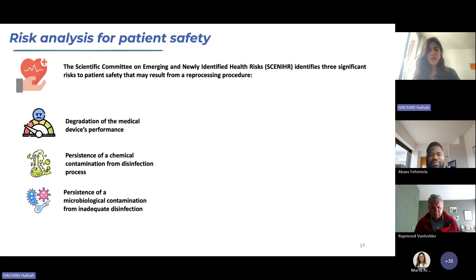So quickly, regarding the risk analysis, the Scientific Committee on Emerging and Newly Identified Health Risks identified 3 significant risks to patient safety that may result from a reprocessing procedure. You have the degradation of the medical device's performance, the persistence of a chemical contamination from the disinfection process, and the persistence of a microbiological contamination from inadequate disinfection. Regarding the degradation of the medical device's performance, in vitro studies have been conducted by Novaflux to demonstrate that there is no significant decline in the membrane's purification ability up to 40 uses. And this has been confirmed for the total cell volume, the clearance of small and medium molecules, the hydraulic permeability of the membrane, and albumin leakage.